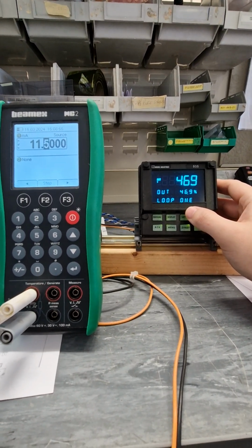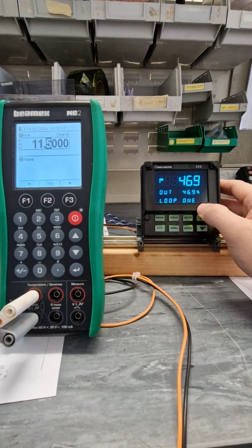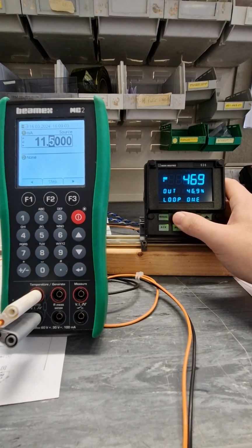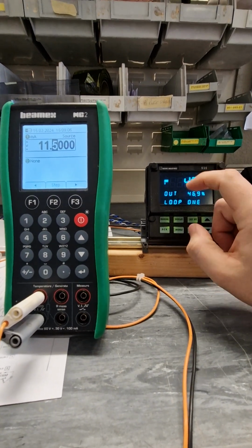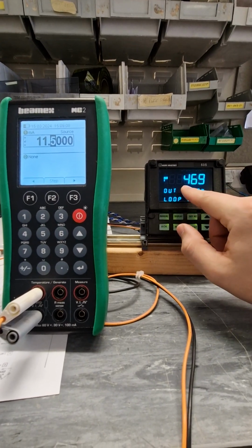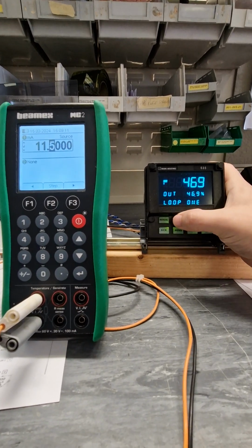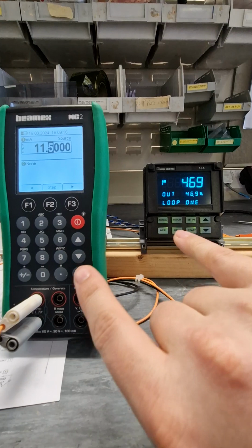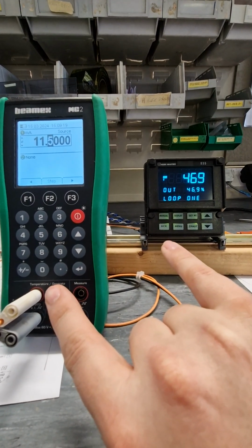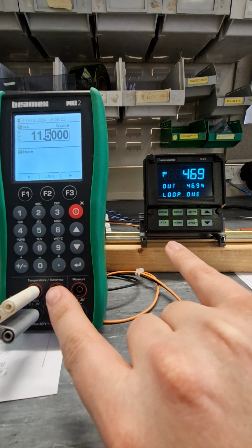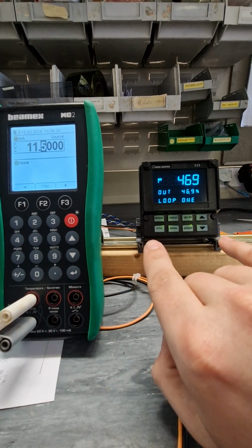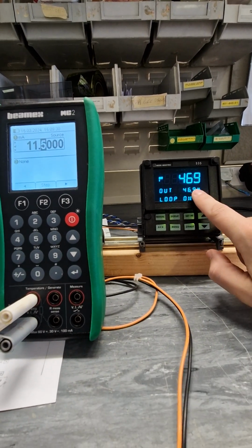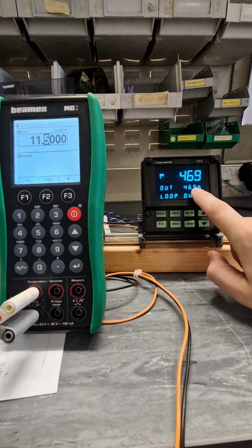PID trip set, and the number of PID is 2. So when the deviation gets to 1, we're set 0 to 1,000 here. If we have a deviation of 1, it will switch from normal PID proportional mode, just proportional, to a very hard P of 1,000 when it gets above the deviation from the set point.